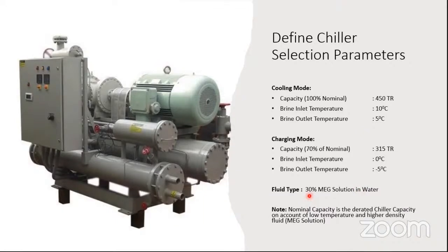Let's say a 30% monoethylene glycol solution in water is what I'm using. So that also he needs to know to select his chiller. He needs all these parameters, the chiller selection parameters. Okay, we need to be aware of something here: nominal capacity is the derated chiller capacity on account of low temperature and high density fluid.